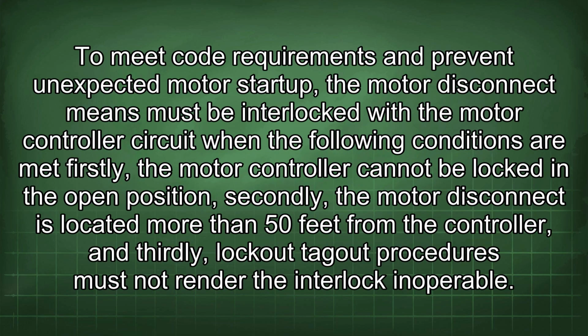To meet code requirements and prevent unexpected motor startup, the motor disconnect means must be interlocked with the motor controller circuit when the following conditions are met. Firstly, the motor controller cannot be locked in the open position. Secondly, the motor disconnect is located more than 50 feet from the controller. And thirdly, lockout-tagout procedures must not render the interlock inoperable.